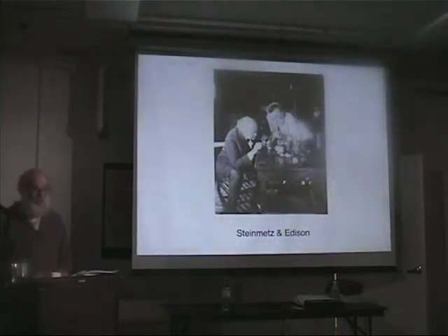The air compressors were all unloaded so the motor could spin freely, and then we attempted to turn one of the kilowatt-hour meters backwards. They call it the kilovolt ampere reactive meter. That measures how much your induction motors and so on are pulling magnetic power out of the system, keeping the wires up. So we created roughly a 5 megawatt reverse wave. The meter was pinned so it wouldn't go backwards, which is what you would expect.